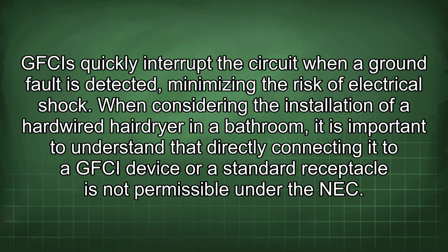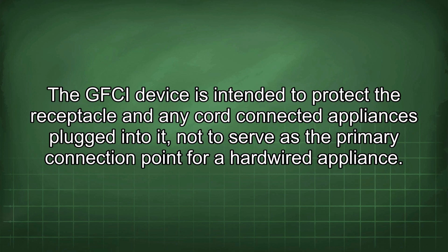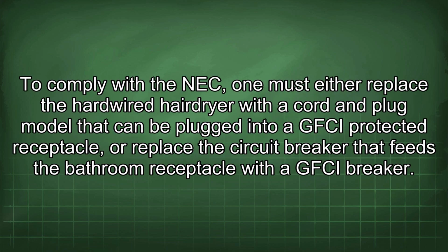When considering the installation of a hardwired hairdryer in a bathroom, it is important to understand that directly connecting it to a GFCI device or a standard receptacle is not permissible under the NEC. The GFCI device is intended to protect the receptacle and any cord-connected appliances plugged into it, not to serve as the primary connection point for a hardwired appliance. To comply with the NEC, one must either replace the hardwired hairdryer with a cord and plug model that can be plugged into a GFCI protected receptacle, or replace the circuit breaker that feeds the bathroom receptacle with a GFCI breaker.